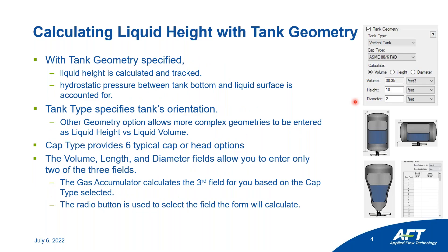One new feature of the gas accumulator is the ability to track the change in liquid height in the gas accumulator during a transient. In order to do that you need to specify the tank geometry inputs. With this tank geometry, a liquid height will be calculated and tracked, and the hydrostatic pressure between the tank bottom and the liquid surface will then be accounted for since we know that liquid height.